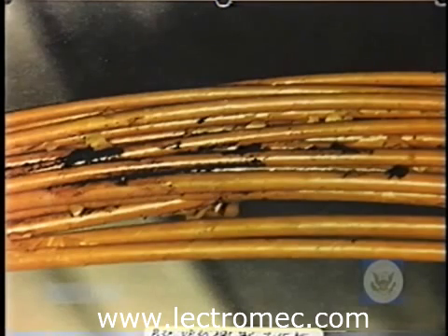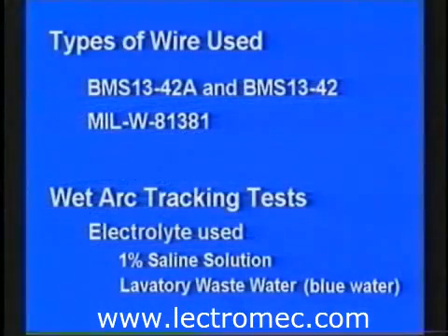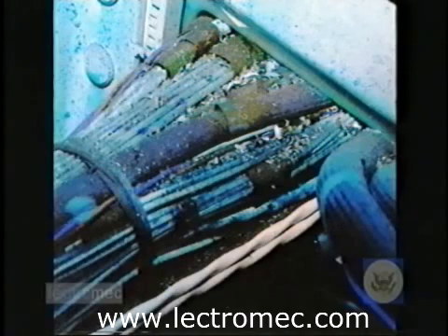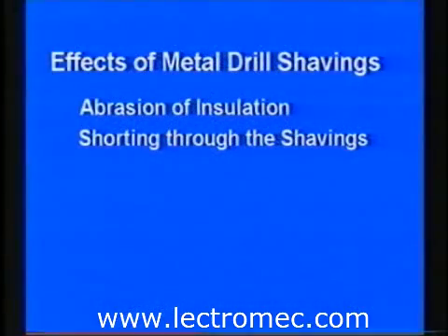This photo shows an example of carbon buildup on 81381-type wire. The electrolyte used for these tests was a 1% saline water solution. Wet arc track tests were repeated with lavatory waste known as blue water. The Safety Board investigation documented numerous cases of metal shavings on wire bundles and between strands, and was interested in examining the effects of metal drill shavings on the wire insulation in abrasion tests. One test measured the damage caused to the insulation by the metal shavings during abrasion, and a second test recorded the properties of short circuits between wires that the shavings created.